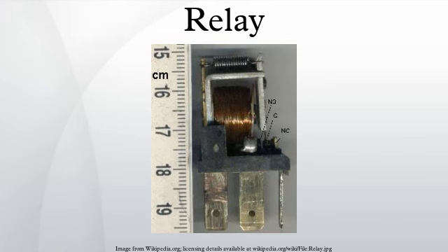Consequently, for relays which may be used to control inductive loads, we must specify the maximum current that may flow through the relay contacts when it actuates: the make rating, the continuous rating, and the break rating. The make rating may be several times larger than the continuous rating, which is itself larger than the break rating.